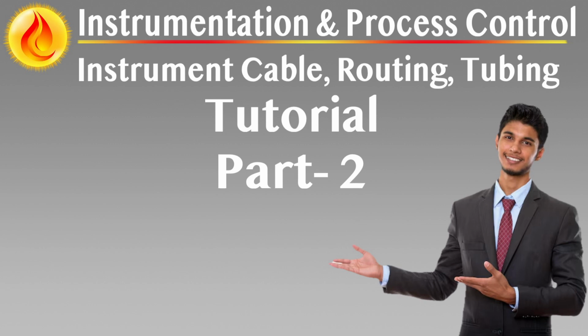Where trays are used, U-shaped designs are acceptable, but ladder-type trays offer reduced shielding and must be limited to non-sensitive applications. All trunking and tray systems must be metallic and electrically bonded across joints and to supporting structures at multiple points using short, low-resistance connections. Supports shall be designed for expected load, spacing, and vibration. Internally, trunking must be free of sharp edges. Bolt heads must face inward, and cable exits must be fitted with protective grommets or bushings.